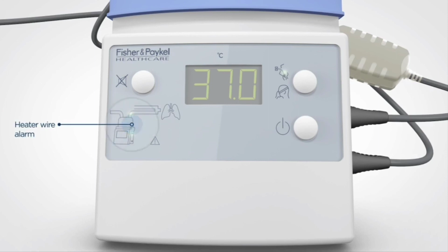Heater wire alarm. Check that the heater wire is connected to both the humidifier and circuit. Check the circuit for damage. Setup warnings. See manual. This indicates a hardware or software fault. Note any error code and send the device for service. Operational alarms. Water out alarm. Check the water level in the chamber and bag. Consider water feed set kinking or back pressure from the flow source.